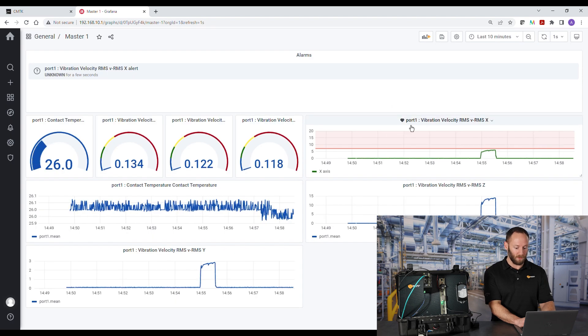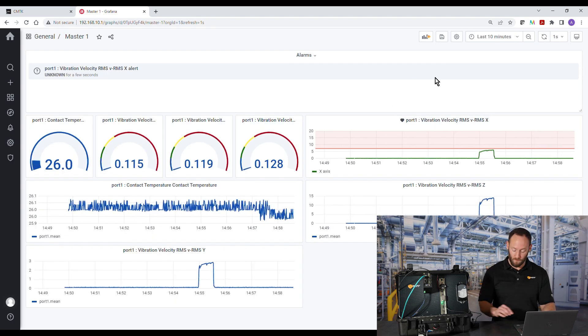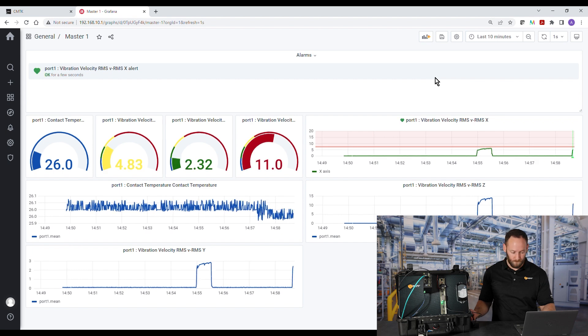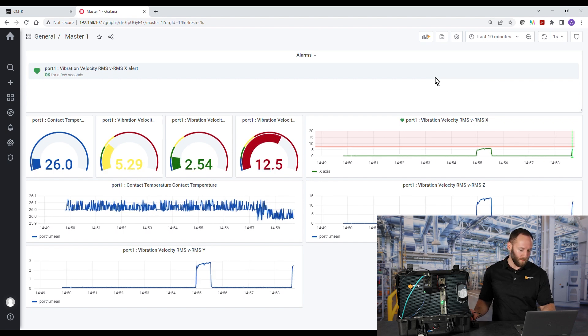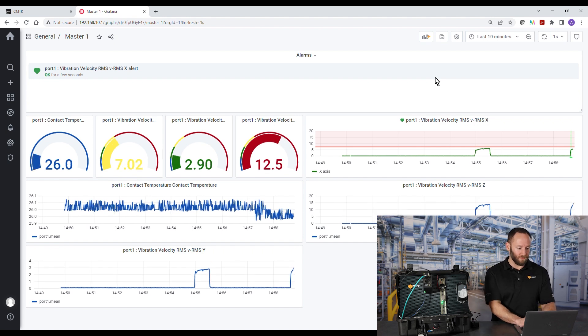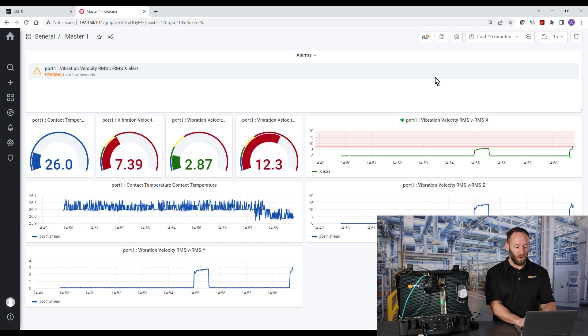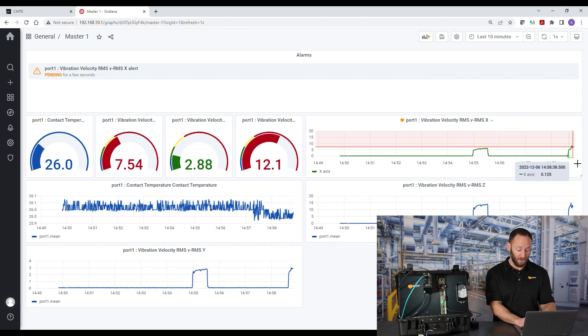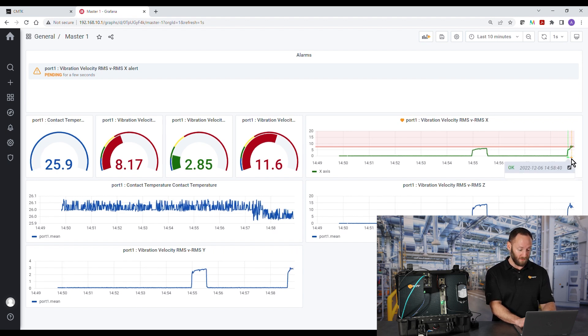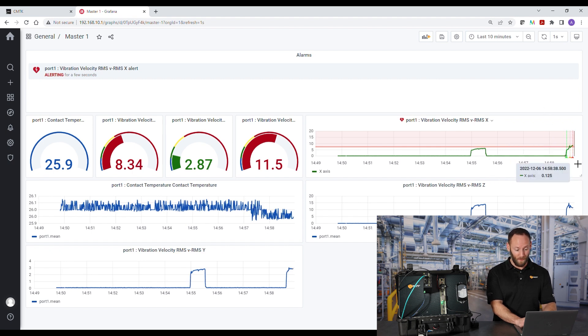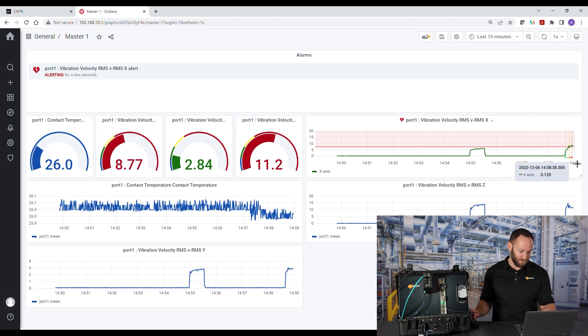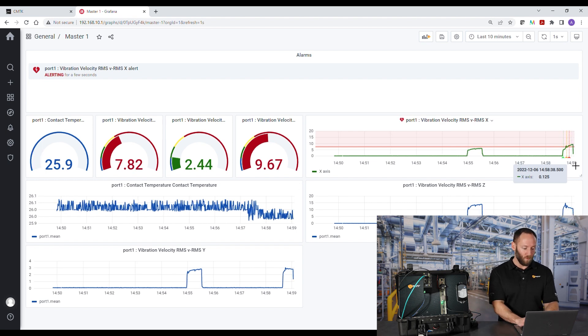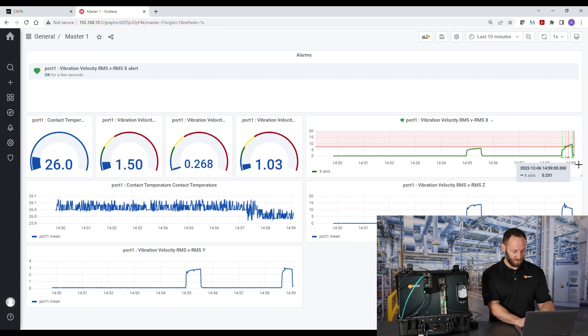So now we've had this set up. We'll hit apply and save changes. Now we see that we have an alert. And when we energize the unbalanced motor. And as soon as we exceeded the 7.1 millimeters on the X axis, we can see the warning is generated. Because we've exceeded the thresholds. And five seconds later, the alarm is set. Now when I turn the motor off, we can see we have an OK condition.